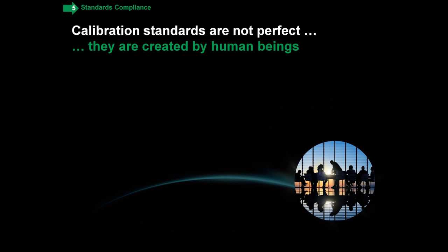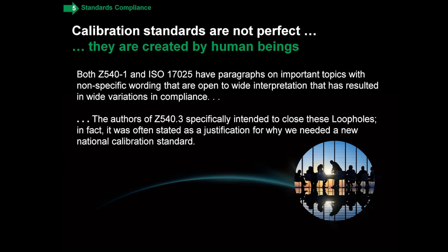Before we get into the specifics on the standards, I just want to make a statement that calibration standards are not perfect. Although all the people on the standards committees try their best, these standards are created by human beings, and the end result — especially with the international standards — is that sometimes you're just not able to agree. Both Z540-1 and 17025 have paragraphs on very important topics with, unfortunately, non-specific wording, and the result is they're fairly open to interpretation.